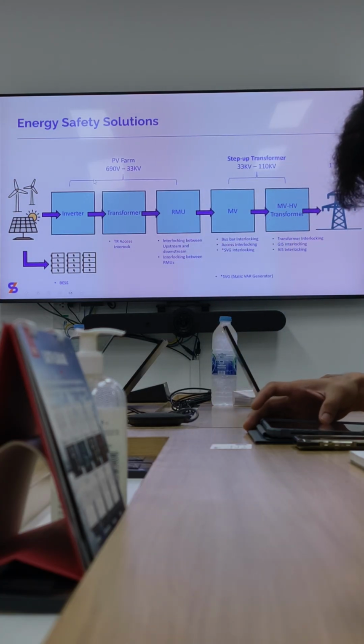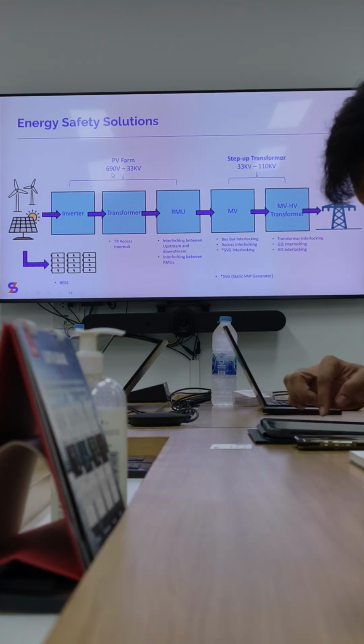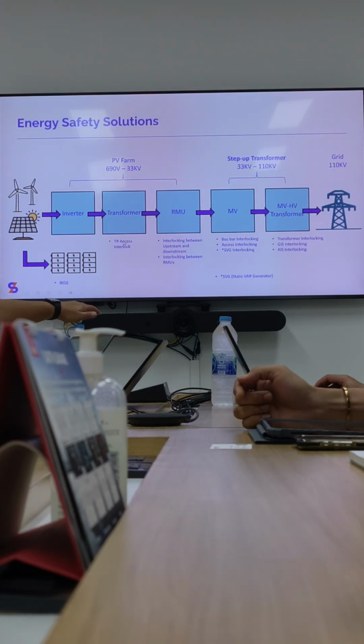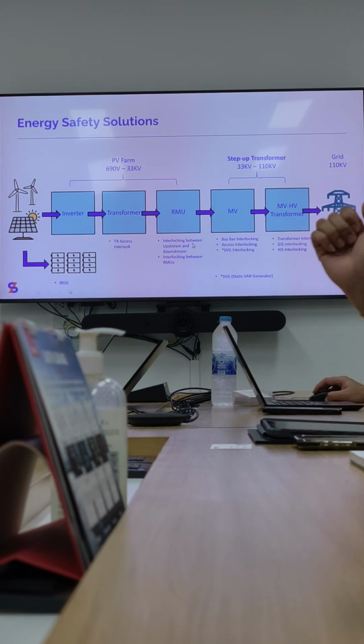Then from here it's something like LV to MV side, mainly on the transformer access, interlock between upstream and downstream on the RMU. On the MV side, bus bar access interlock will be similar with the transformer, SVG similar with the capacitor bank.